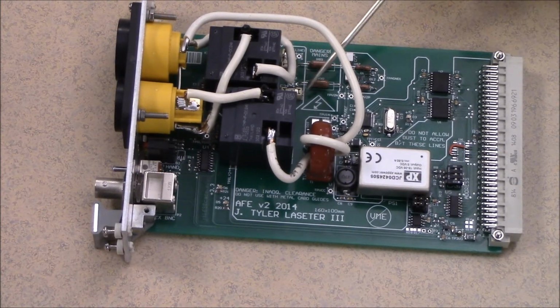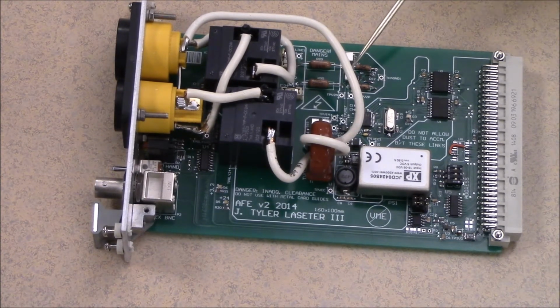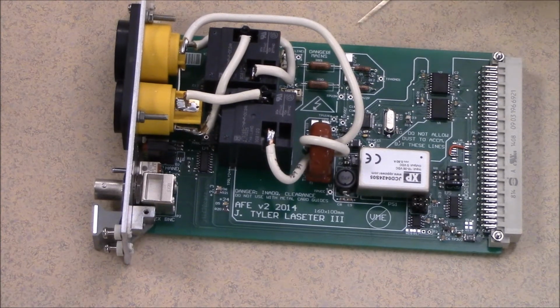The voltage that's picked off before the relays is protected by these two 62 milliamp telecom fuses that prevent any catastrophic failures of the line or extremely large surges from causing any further damage. We have 2 high stability flame-proof 1 megohm resistors that form a differential divider with these 2 1 kilo ohm resistors, which are all matched in temperature coefficient so that the error is kept within ratio with itself so that it does not amplify or attenuate our input based on temperature changes appreciably.